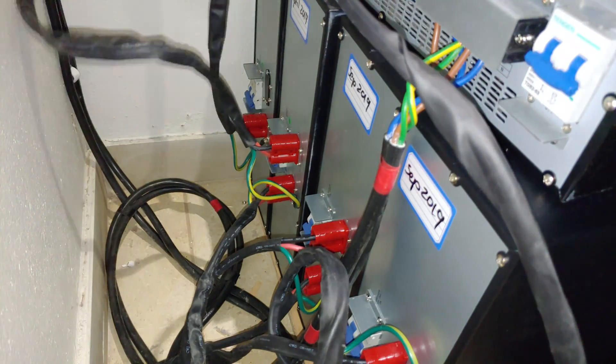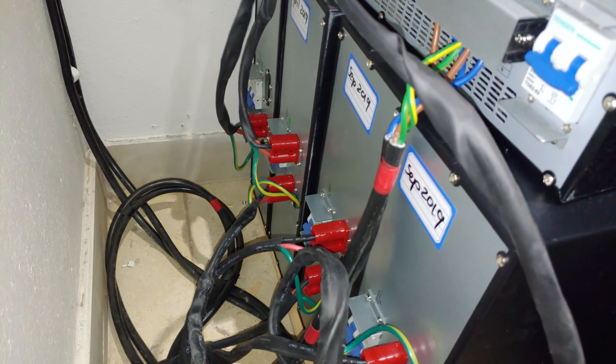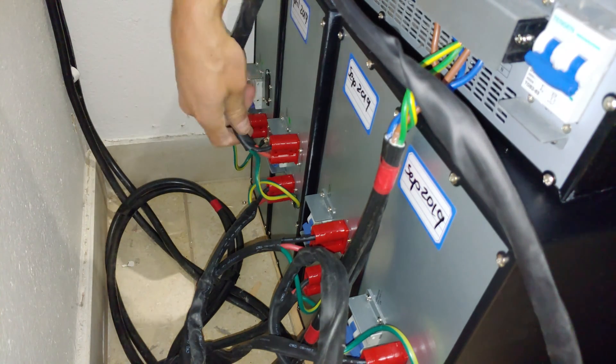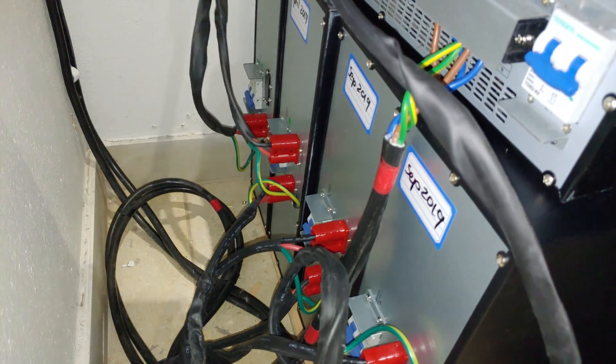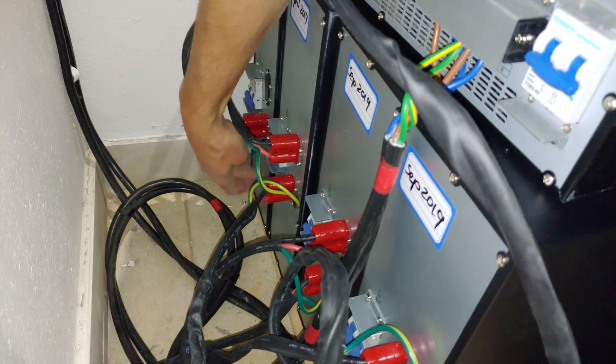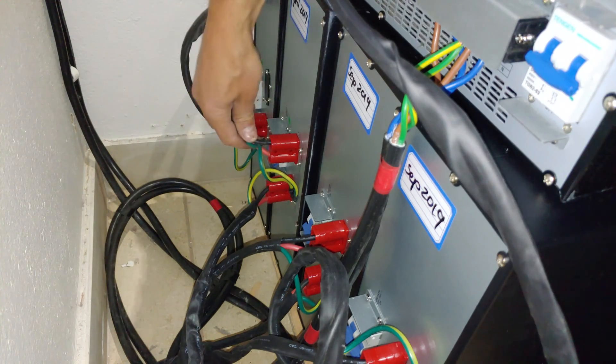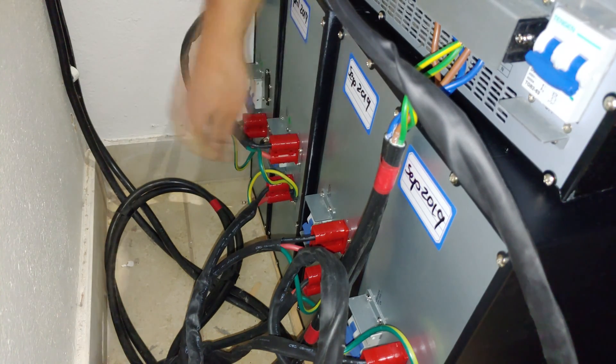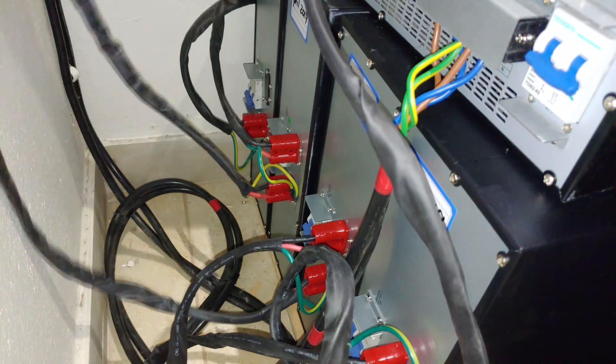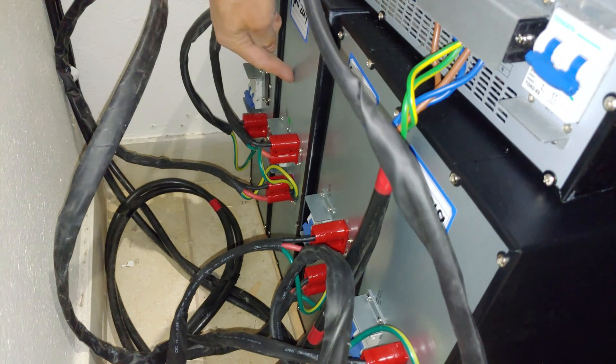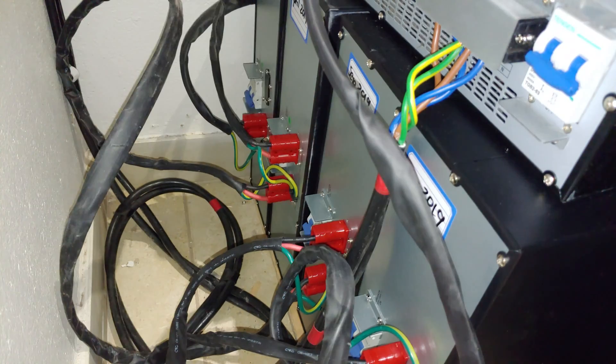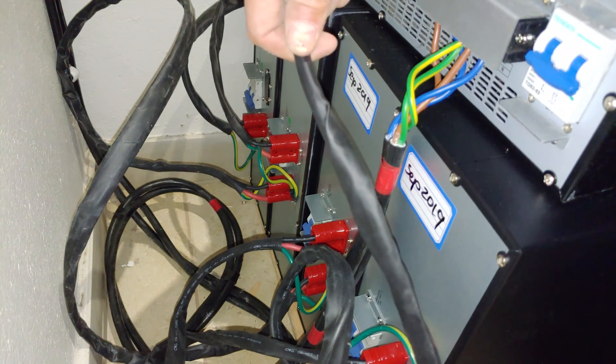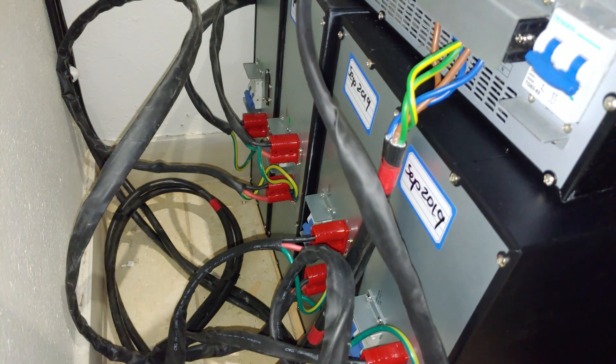If you have a look at this, this is a daisy chain setup. As you can see, there's bank one connected to bank two. The earth is connected to the chassis—there's a little screw there—and you can see it comes here, both screwed into the chassis. You can see daisy chain again. Daisy chain is as follows: what a daisy chain means is you go from one to the other to the other. Why do you do that? Because the UPS has only one power connection for the battery, so even though you've got many battery banks, they have to be connected in daisy chain formation.